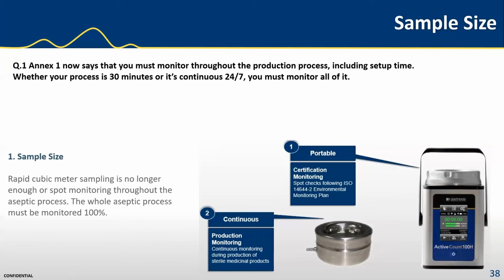And I guess it's a bit of a shift in mentality, because a lot of companies were just getting a cubic meter sample for the viables to satisfy the standards. But you must realize that there is a requirement in Annex 1 to capture all events. So continuous really is the way to go. So good question, and definitely look into the options out there for viable sampling with active air samplers and continuous systems. They are out there, and I'd recommend that you do consider them in relation to EN 17141 and also the obsoleted ISO 14698 standard, which is a good standard for selection of microbial devices.